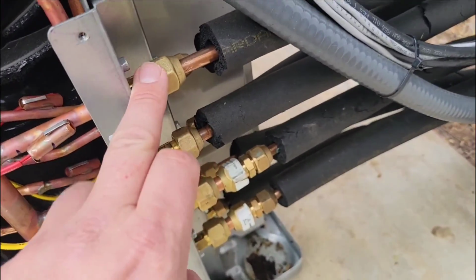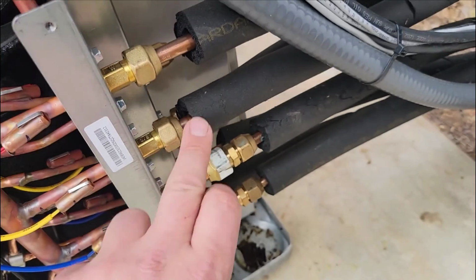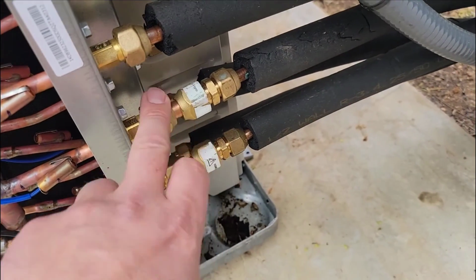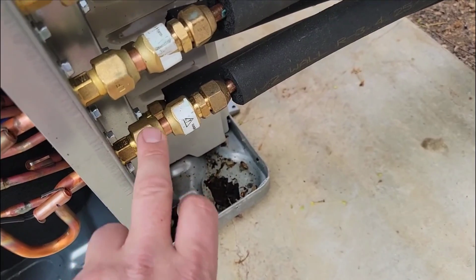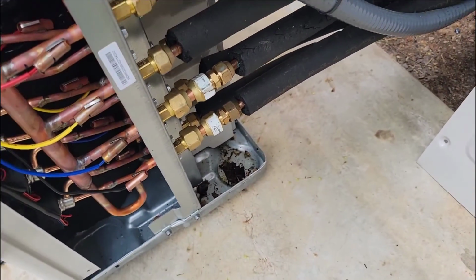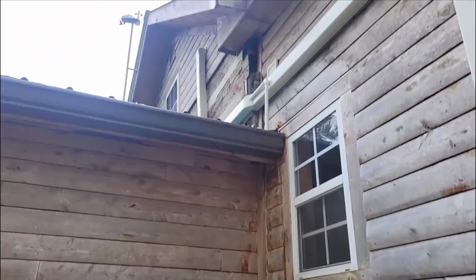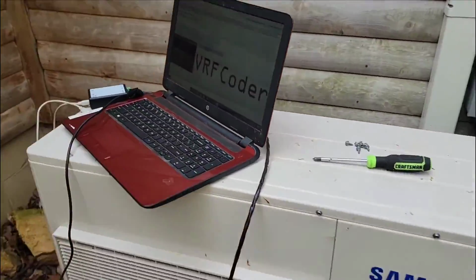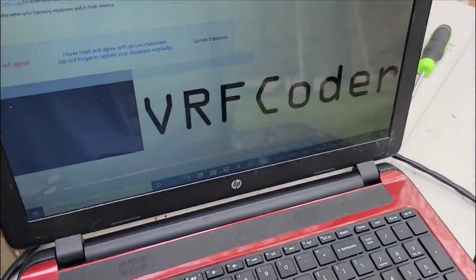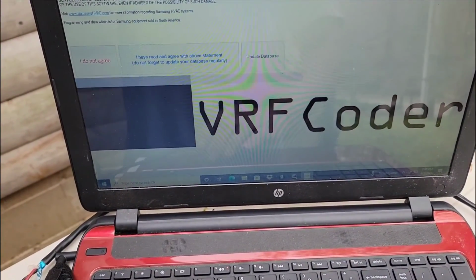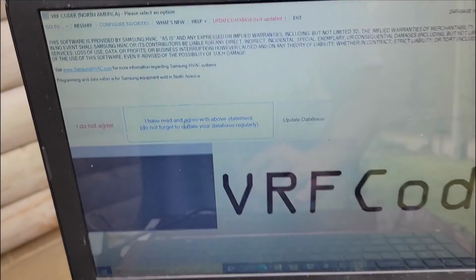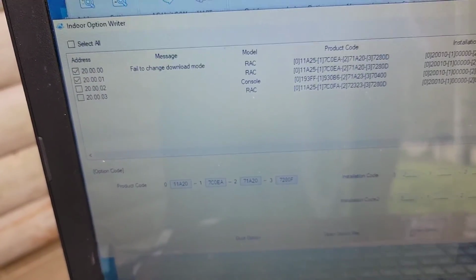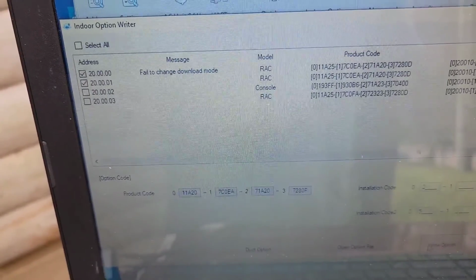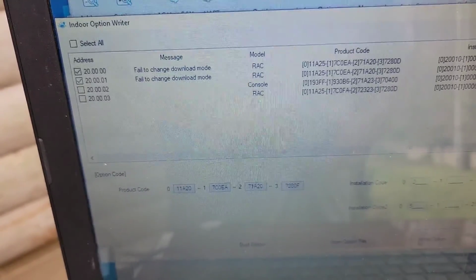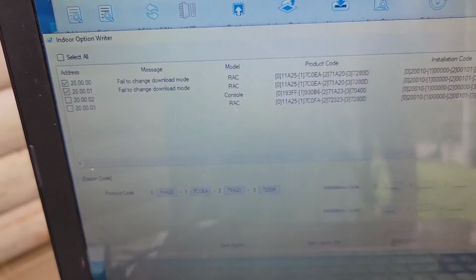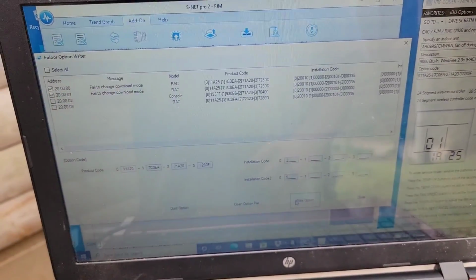So for me, I've got the 2 9s on the top pipe connections. Then the third one is the console, and then the fourth and last is the 1-ton 12,000 BTU head that's upstairs. So now that I know exactly what I got, I'm gonna get on VRF Coder and get the option codes that I need. Oh, fail to change download mode. Uh-oh, got a little problem.